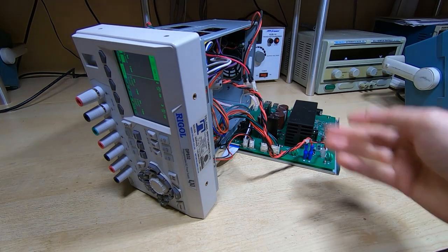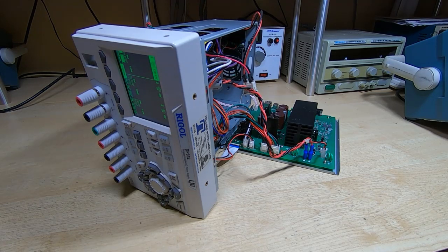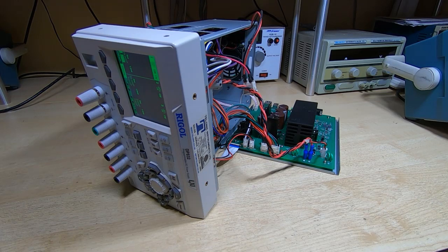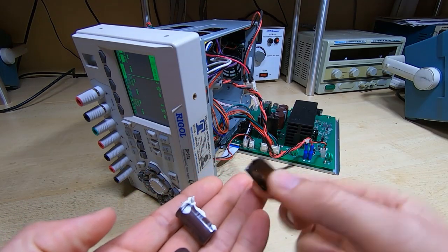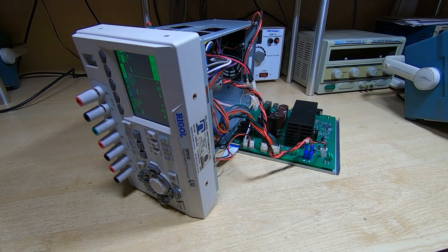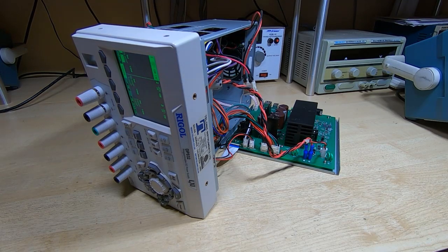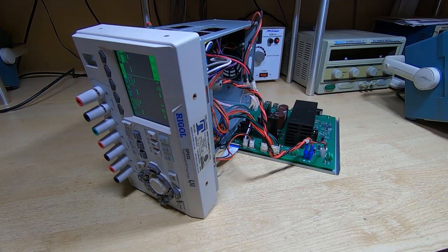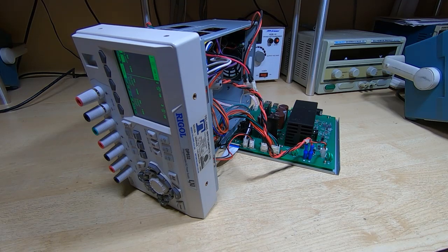I did modify it. I replaced the heatsink with a bigger one, replaced the capacitors, I also replaced the regulator as well, but that didn't stop it resetting itself. It was still rebooting and it was getting gradually worse again. It turned out, as in the previous video, that the fault appears to be on the actual digital control board.